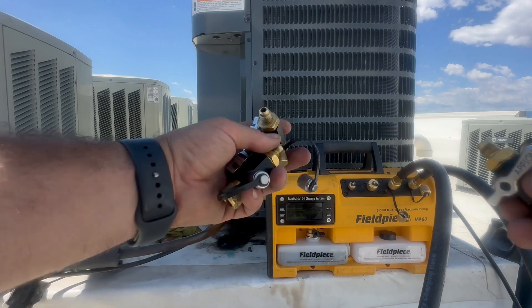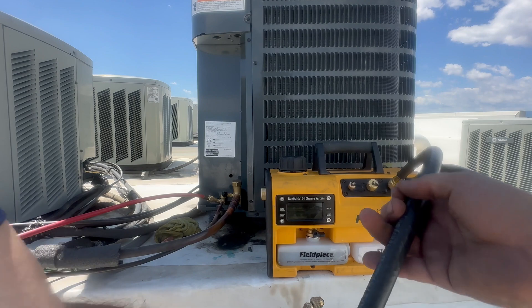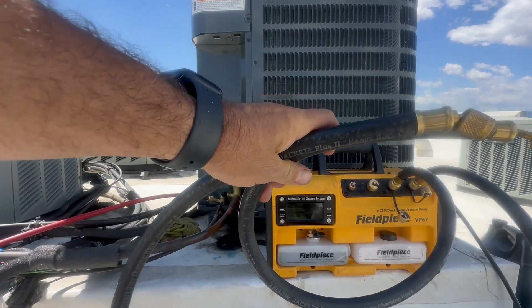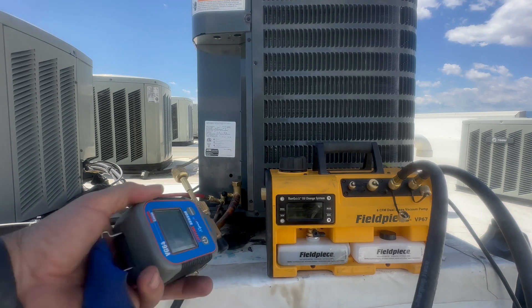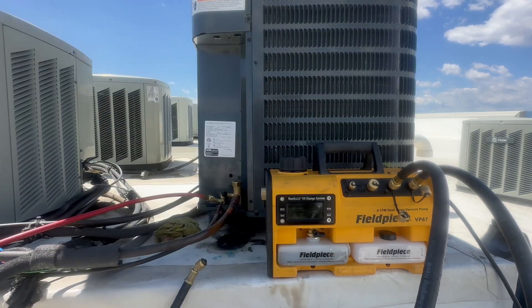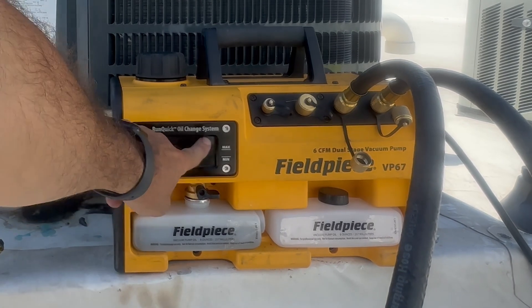Tools I'm using for evacuation are three Appion valve core removal tools, two Yellow Jacket 3-Ace hoses used for evacuation only, the BG64 micron gauge with the Yellow Jacket micron coupler, and the VP67 dual stage vacuum pump with fresh new oil.